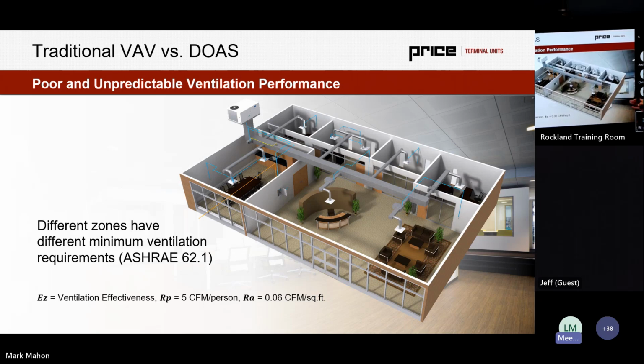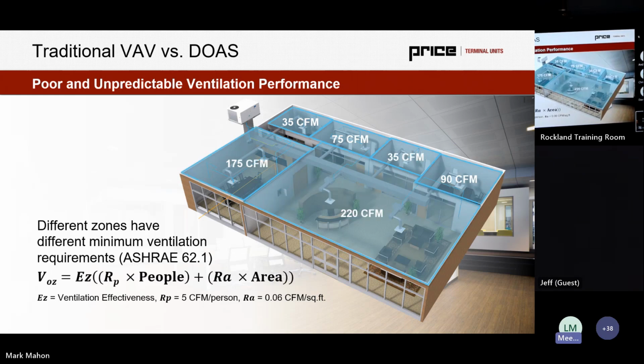And we have different zones that have different minimum ventilation requirements per ASHRAE 62.1. So this is going to be based off of the ventilation rate per person, the ventilation rate per square foot within the space, and then also how effective we are at actually mixing air into the breathing zone within that occupied zone. So in this case, with an open office, we're looking at 5 CFM per person and 0.06 CFM per square foot as the requirements from ASHRAE.